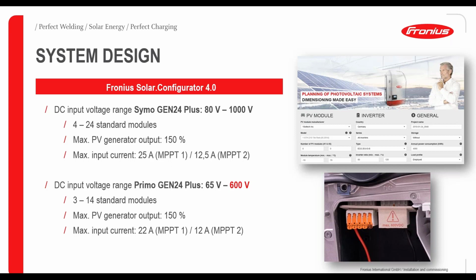because there we can see if we are in the right voltage range, if we are not over-dimensioned too much, and so on, in one click, more or less. So it's a very fast method. What I want to mention is that on the Symo Gen24, we have a very wide input voltage range from 80 volts up to 1000 volts. So we are talking about standard modules from 4 to 24 modules, which we can connect here.